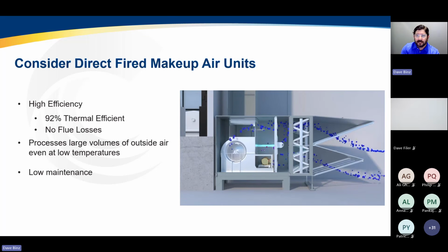So the technology solution that we show there in these industrial retrofits is tempered ventilation through makeup air units. And in these large industrial spaces where I have high volumes of CFM, we're talking 50,000, 100,000, maybe even 500,000 of total CFM required to meet my pressurization because of the process. I want a solution that's going to be cost-effective on first cost and cost-effective on operating cost. And that's really where direct-fired makeup air shines. So direct-fired, in a sense, is combining the ventilation with my gas directly and heating that through natural gas. It's a 92% thermal efficient combustion process.